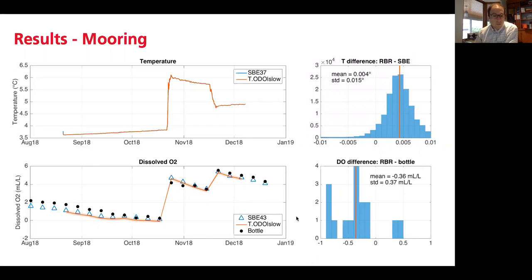But then when we look a little closer, we see that two things are true. One is that the Seabird, which is the triangles, is also always lower or biased low compared to the water bottles in the same way that the RBR is. And we see that before this large mixing event, and then after the mixing event, everything is more aligned. And so what we're expecting here is that there's a bit of vertical stratification where the oxygen level is a little bit lower, deeper down where the RBR is located, and even where the Seabird is located on the rosette compared to the water bottles, so that both the Seabird and RBR are showing lower values than the water bottles before the mixing event. And then after the mixing event, everything is lined up well. And when we do the difference measurement between the RBR and Seabird and between RBR and the water bottles before the event, we see there's a larger difference, and after the event, it's a tighter fit.